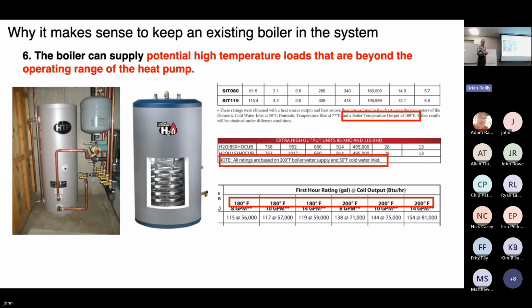It just shuts the heat pump off. And if you reset it, it'll just go through the same cycle again. So you've got this thermal bottleneck based on the coil. And quite honestly, today, the North American indirect tanks, with a couple exceptions, the coils are pretty small because they were designed around boilers. And look at the ratings. These are taken right out of the ratings table. First hour ratings based on coil temperatures of 180 and 200 degrees Fahrenheit. Okay. Heat pumps, just current generation heat pumps just can't get to those temperatures.